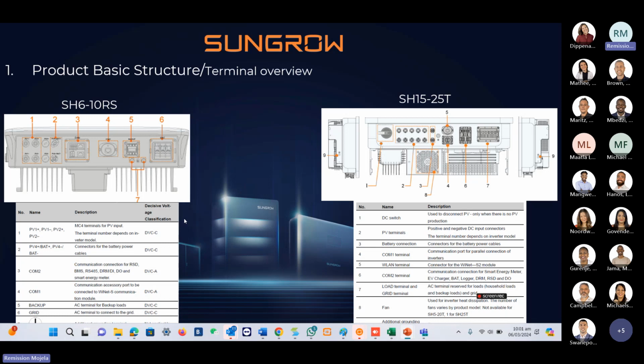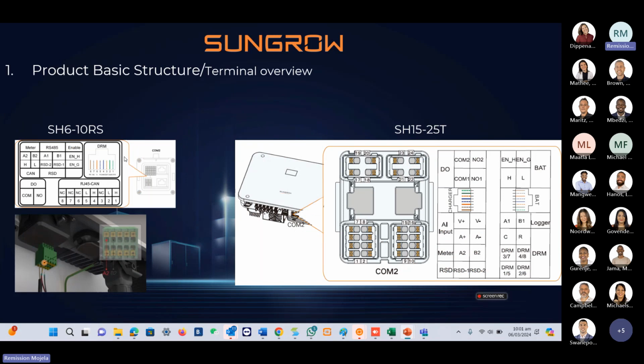Then, as I was saying, that's basically it: the connection, the PV, the battery, the comms from the inverter to the meter, the comms from the battery to the inverter, and then the communication module that gives you access into the inverters. By the way, the only way to be able to communicate with these inverters is to have the communication module. Hence, it's part of the package. It has to be plugged in for you to have access into the inverter.